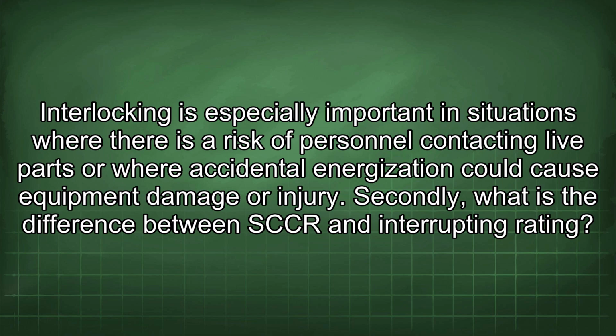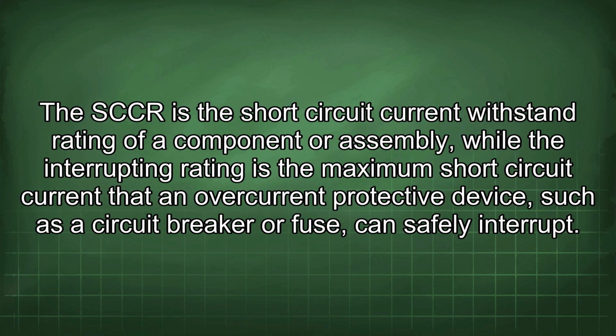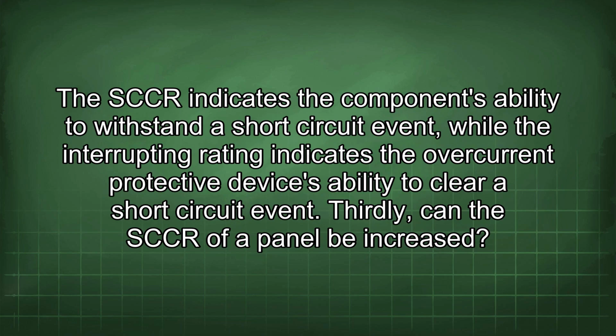Secondly, what is the difference between SCCR and interrupting rating? The SCCR is the short-circuit current withstand rating of a component or assembly, while the interrupting rating is the maximum short-circuit current that an overcurrent protective device, such as a circuit breaker or fuse, can safely interrupt. The SCCR indicates the component's ability to withstand a short-circuit event, while the interrupting rating indicates the overcurrent protective device's ability to clear a short-circuit event.